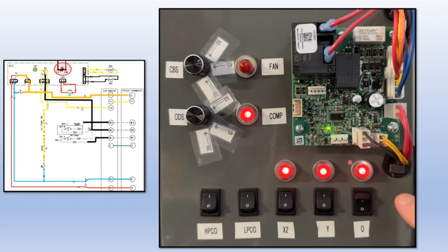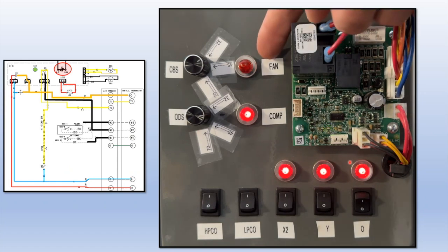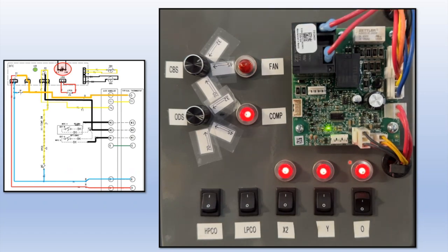You're going to immediately see that the reversing valve is now energized, changing the flow of refrigerant. So the indoor coil is now the cold coil, absorbing heat energy from inside, putting it into the refrigerant, and making the outdoor coil the warm coil to help melt that frost. You'll also see that the fan was shut off on the outdoor unit. This is so that the cold air going past the coil isn't fighting your defrost.